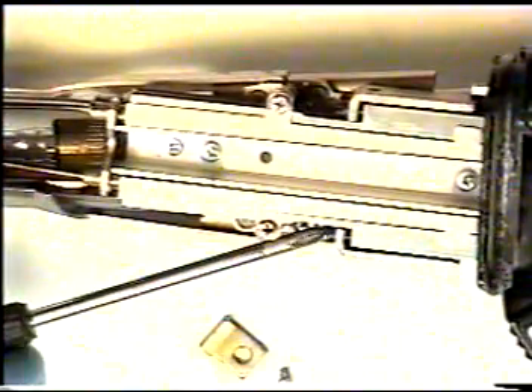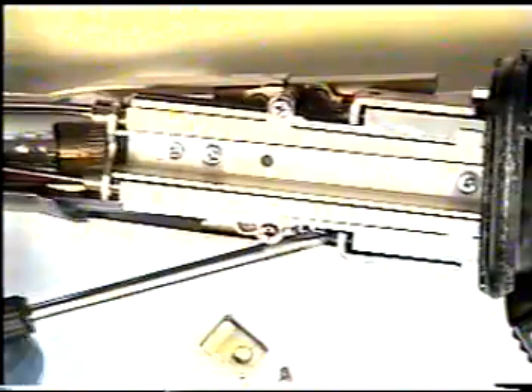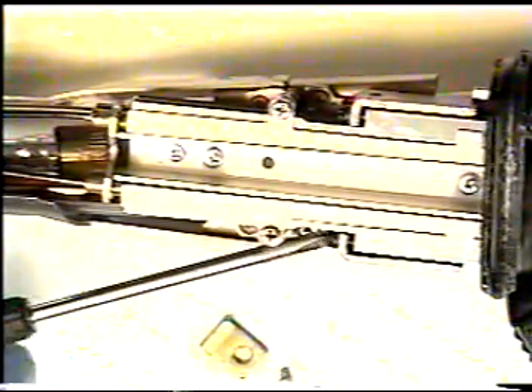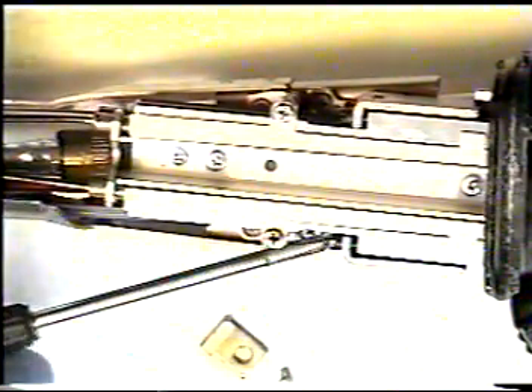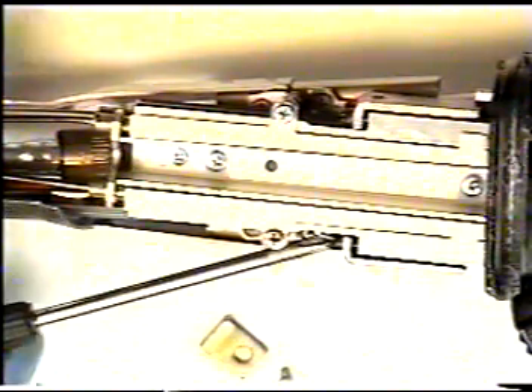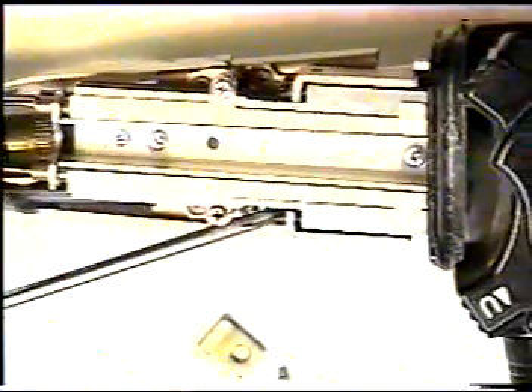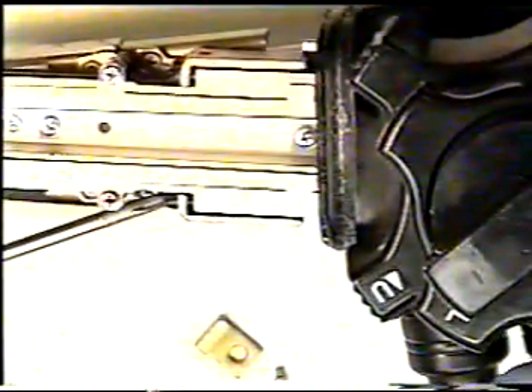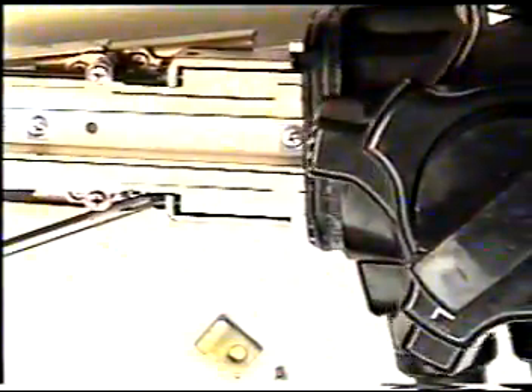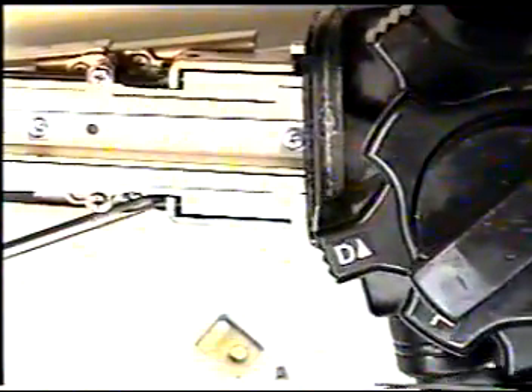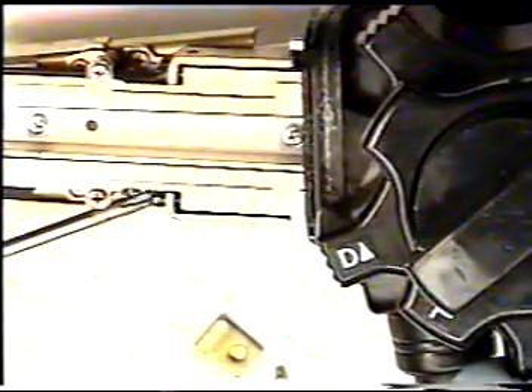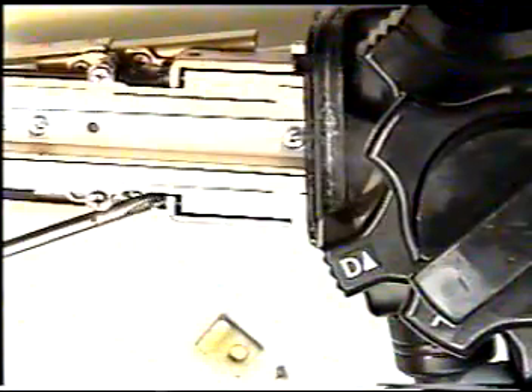This scope will require a 90-degree down angulation adjustment, and the left and right angulation will need to be adjusted to 100 degrees. To obtain these angulation adjustments for up, down, left, and right, it will be necessary again to turn these angulation control cams to meet the required manufacturer specification on angulation. The cam will be turned either clockwise or anti-clockwise. Moving the up, down, and left, right knobs to their fully extended position, you will adjust this cam again until it meets the required angulation.